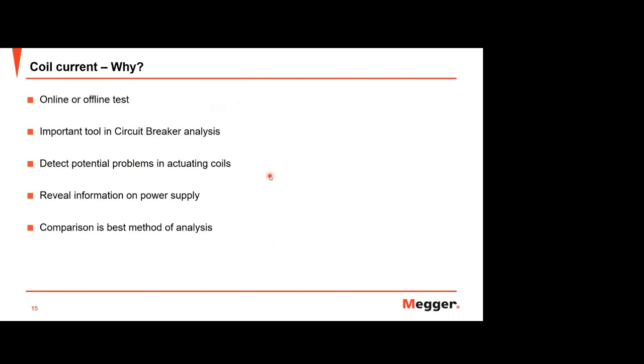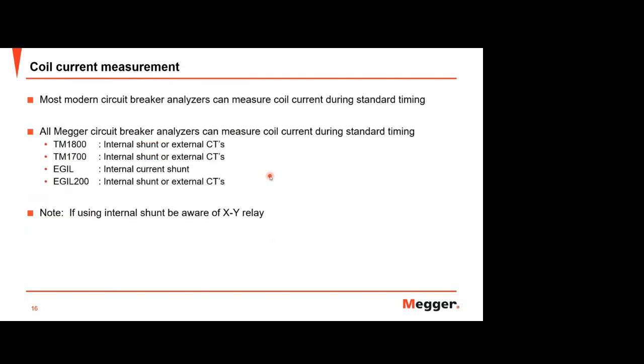Okay, and next, this is the coil current measurement. I believe many products can do this measurement, and Megger can also do it. Most modern circuit breaker analyzers can measure coil current during standard timing or conventional timing. At Megger, we have some products: the TM1800, TM1700, EGIL, and the new EGIL 200, which are also equipped with coil current measurement. It can be measured with an internal shunt or with external CTs. But we can do this measurement through the Megger circuit breaker test.